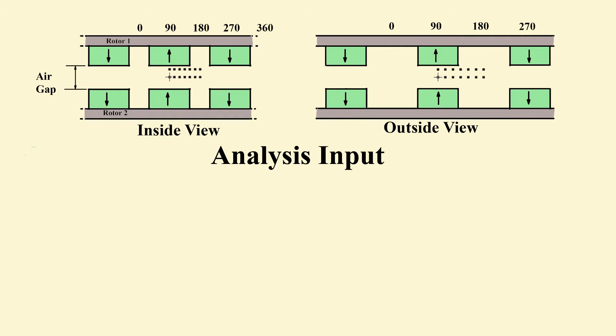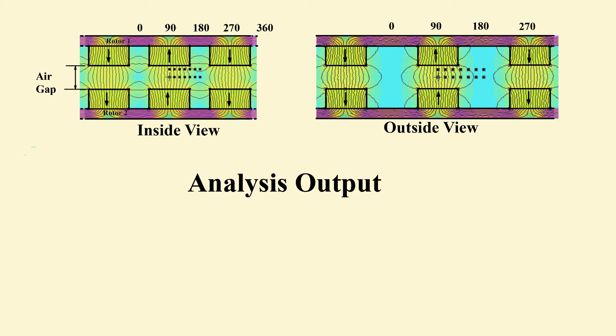Scale drawings plus air, magnet and iron properties are entered into the program. Points are set in the air gap at 15 degree intervals over 90 degrees. Just press the button and the flux density is mapped. Numeric values can be read off at the set points.